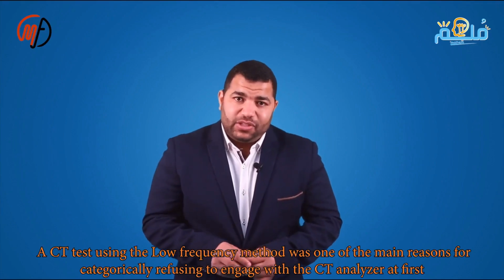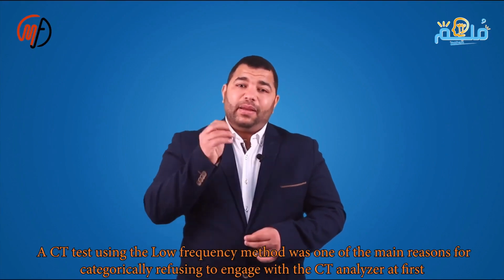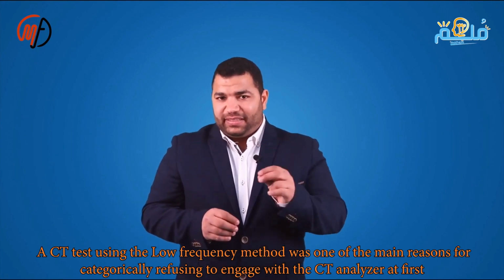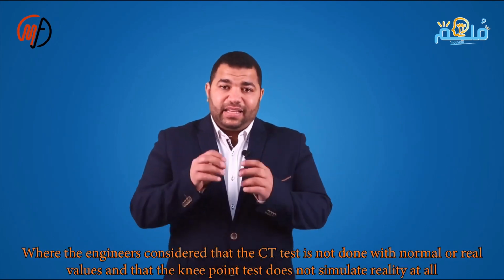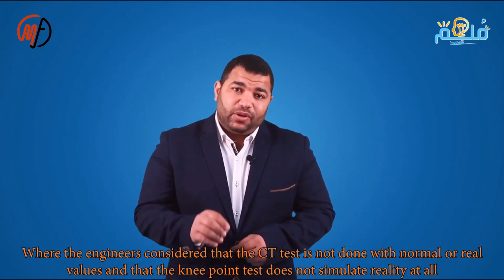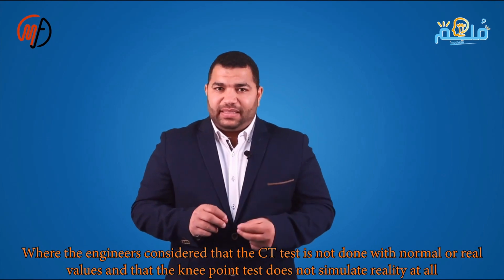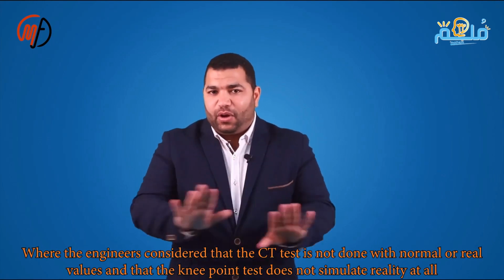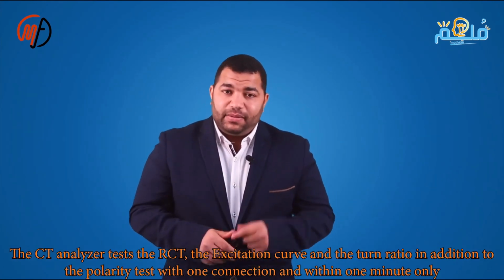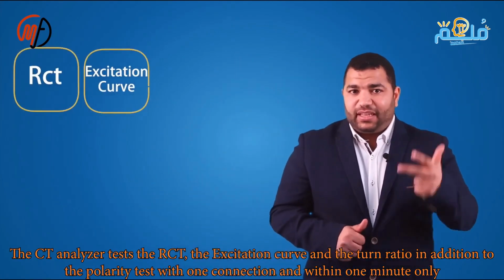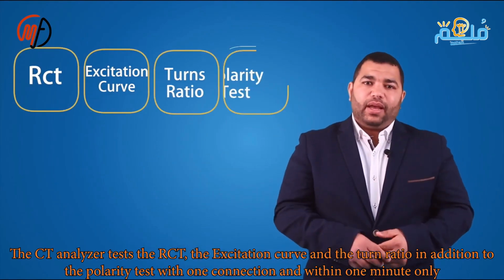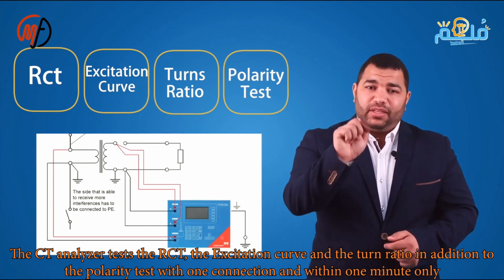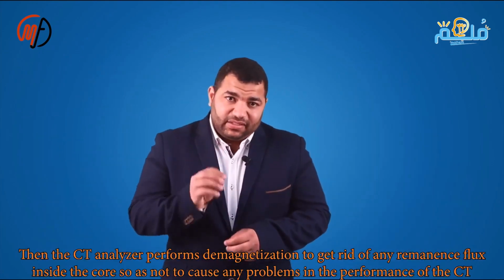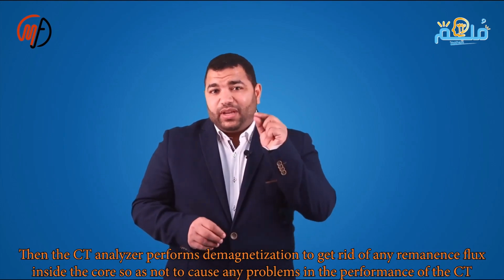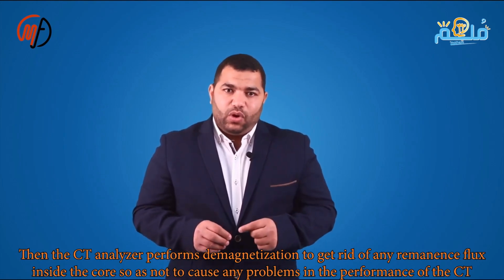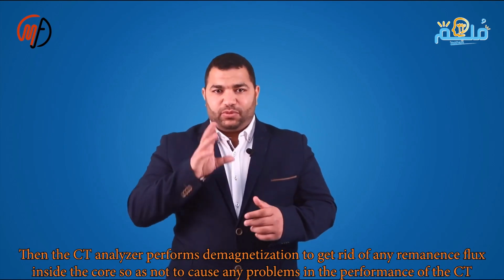The CT testing using the low-frequency method was one of the main reasons for categorically refusing to engage with the CT analyzer at first, as engineers believe that CT testing does not occur with normal real values and that the knee point test does not reflect reality at all, which is done in the CT analyzer. With the RCT test, the excitation curve, the ratio, and the polarity test, all done with a single connection in just 1 minute, the CT analyzer then performs demagnetization to eliminate any remanence flux inside the core to avoid any issues with the CT's performance.